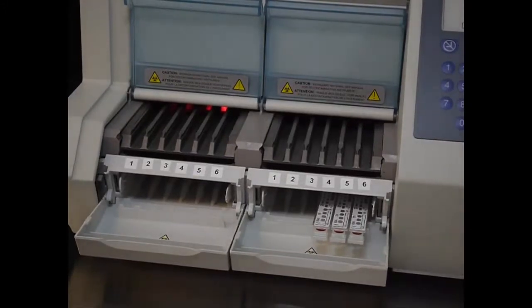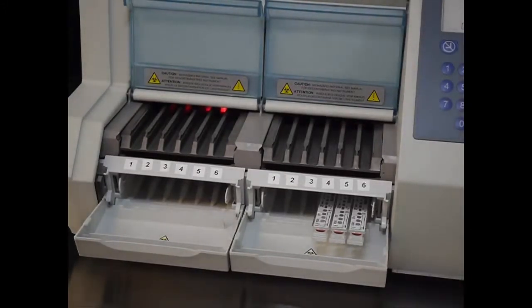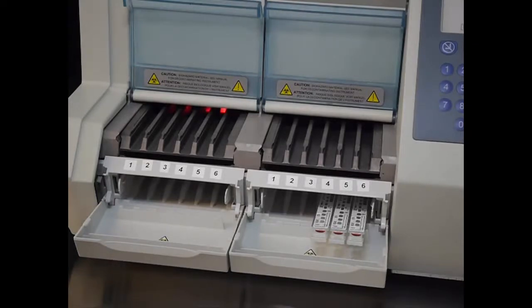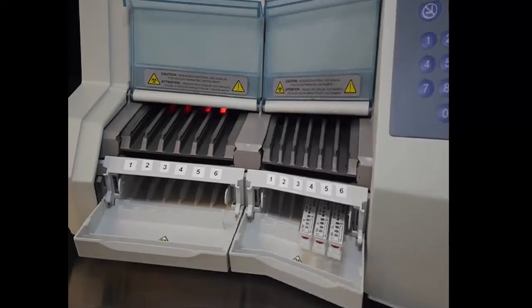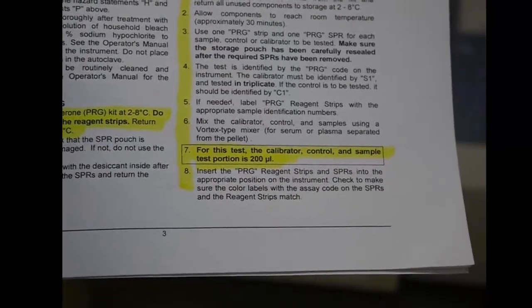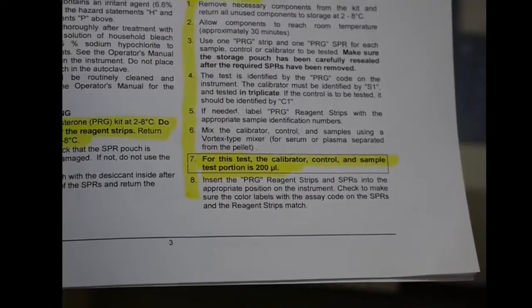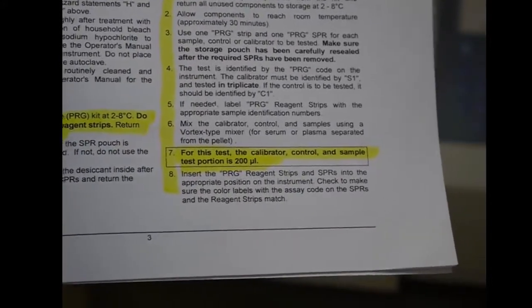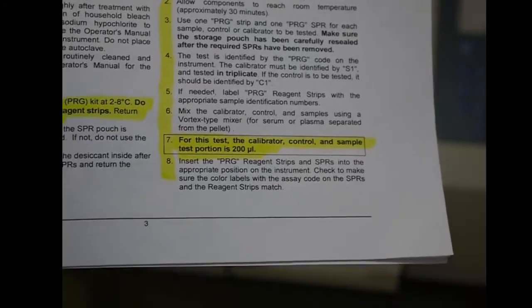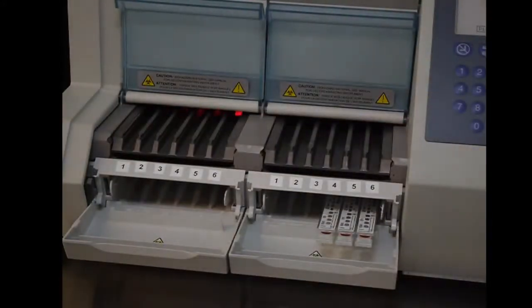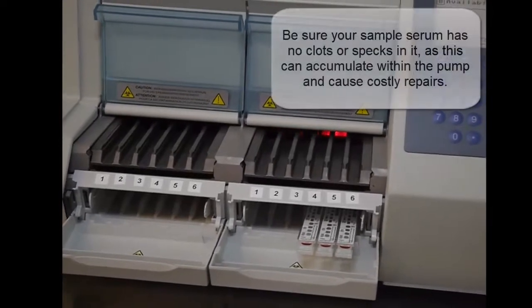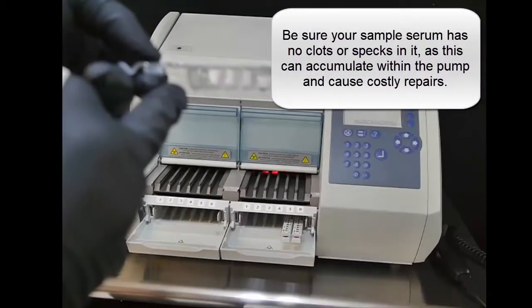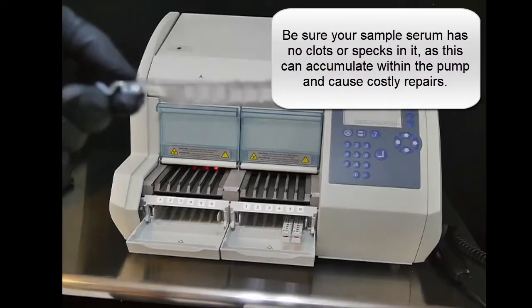As you can see here, I have 3 test strips that are warming to room temperature. The compartment they are in is called the test preparation tray, and this just helps keep them in place as they do tip easily. They are sealed, so none of the contents will leak unless punctured. Again, for progesterone assays, the amount of serum for calibrator, the S1, the control, C1, and any sample portion is 200 microliters. Now that my components are at room temperature, I will pipette 200 microliters into the first well, being careful to avoid bubbles.